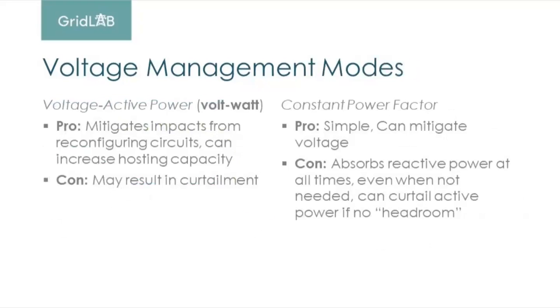So the other mode we'll talk about briefly is constant power factor, which I talked about before. That's a pretty simple, straightforward setting. I like this setting in some ways, because you can set the device to essentially run all the time at a certain power factor. There have been a lot of good studies, probably about 5-6 years ago, like SDG&E ran a bunch of studies looking at volt-var versus constant power factor. Really the downside with constant power factor is that it only works in one direction. So you either have to set it to leading or lagging. Generally, you're going to absorb reactive power. But the other issue is that it's going to be running in that mode all the time, even when it's not needed. So even if there's not a voltage issue on the circuit, it's still going to be using reactive power all the time, which does put wear on the inverters.